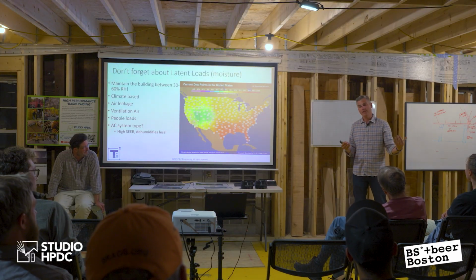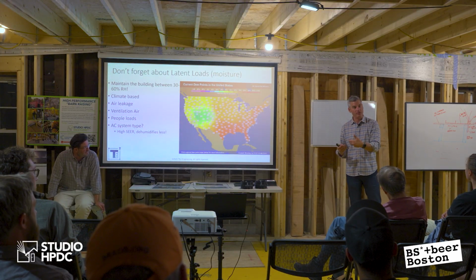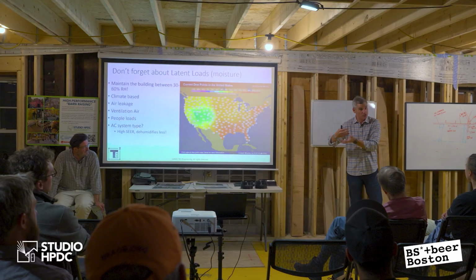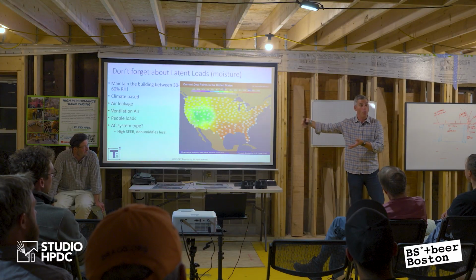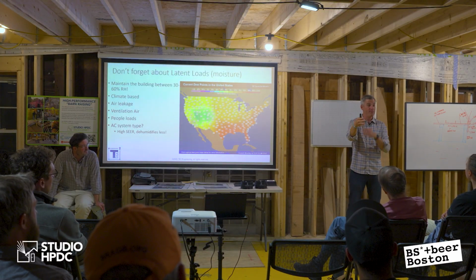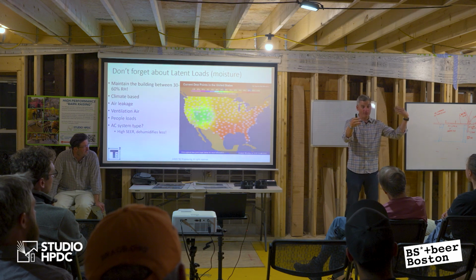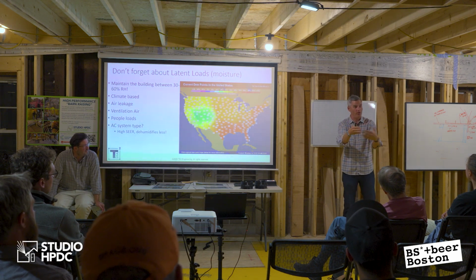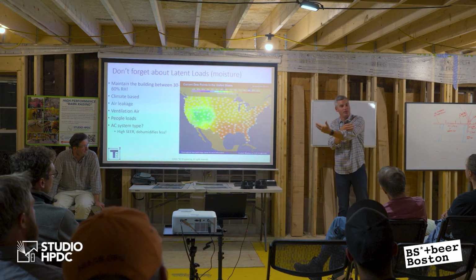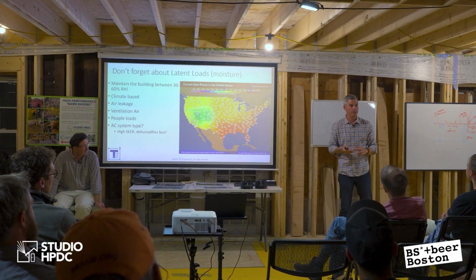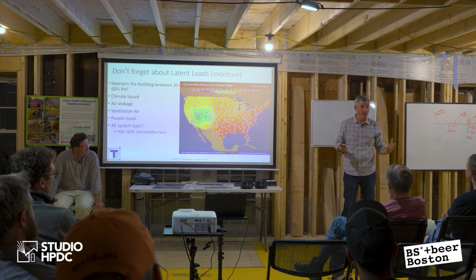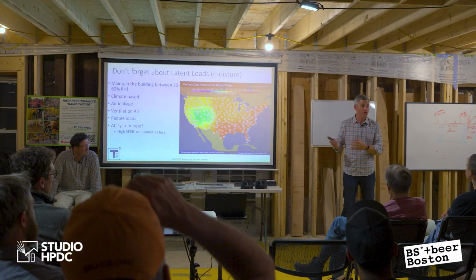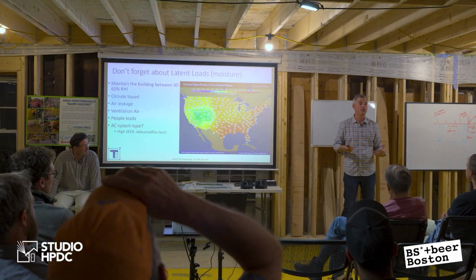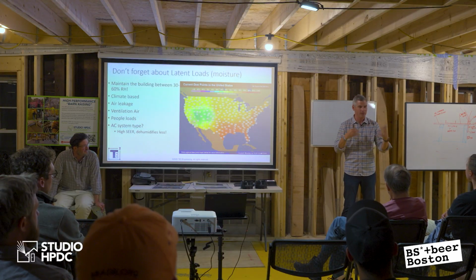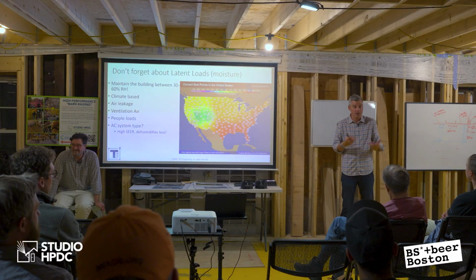And so we either duct those ERV supply fresh airs into the return of a ducted system so it can post treat it, or you can put a coil in, make that coil warm, and therefore that 55 degree air goes across a warm coil, 100 degrees or whatever, and comes out nice and warm on the discharge side, so it feels comfortable when it's blown back into the space. So it absolutely can be done, and it can be very easily done on an air to water heat pump. It'd be very hard to do that on a traditional refrigerant mini split VRF type system, but it can definitely be done.